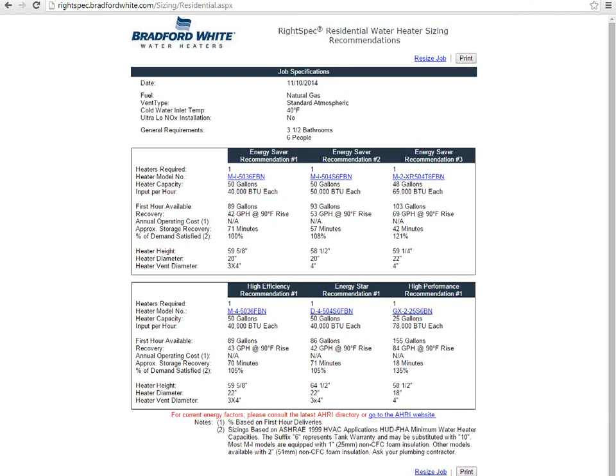The 25-gallon is gone now. It's still on here, and it's recommending it. I don't know why. But the GX series heaters, what they did is they took their light commercial version of the Icon gas valve, and they started doing this, and they send it with a mixing valve setup. So now what we can actually do is we can store at 180 degree water temperature in there, mix down to 115, 120 degrees, and get crazy amounts of first hour availability out of it. All right, let's switch back over.